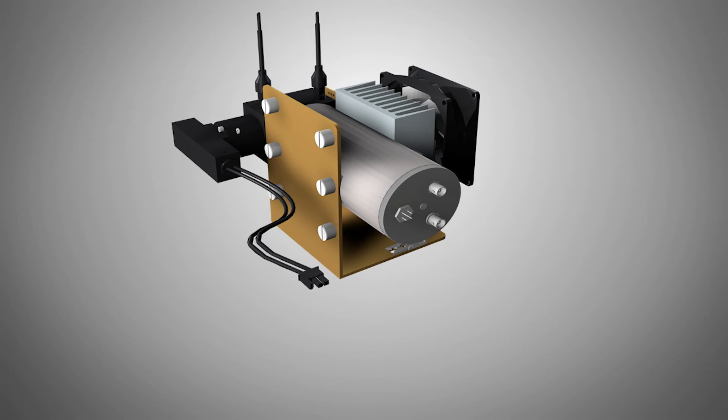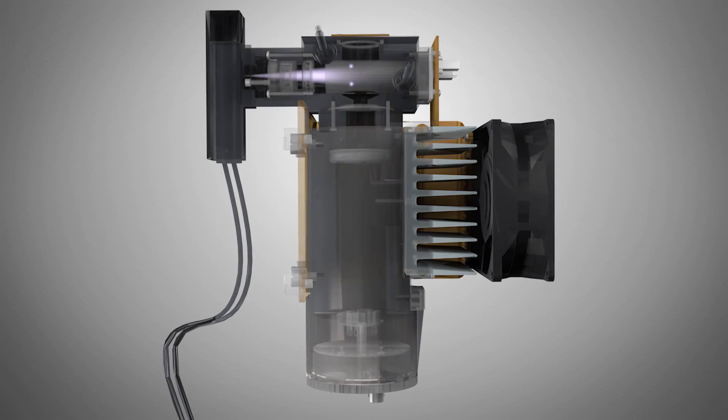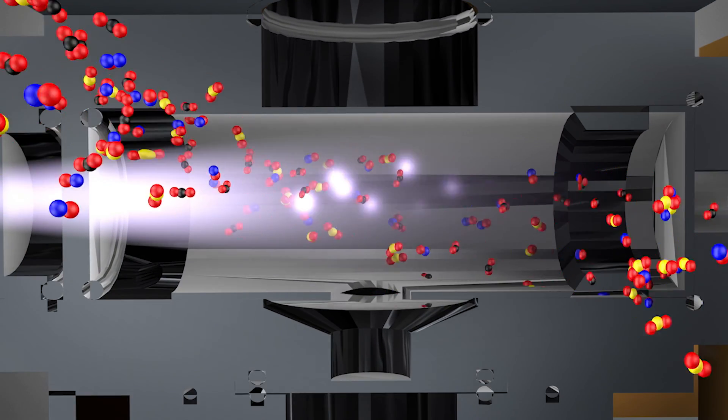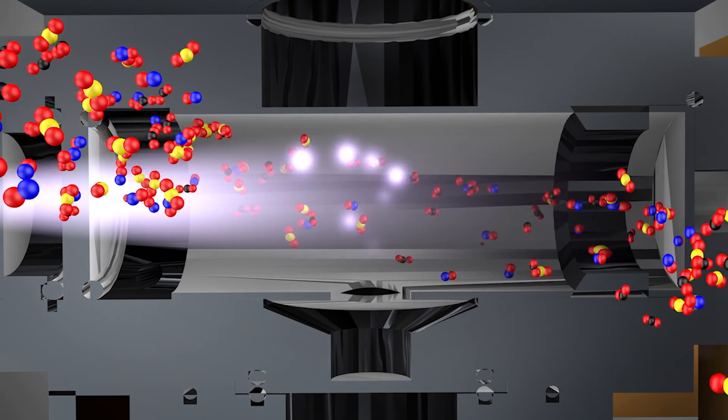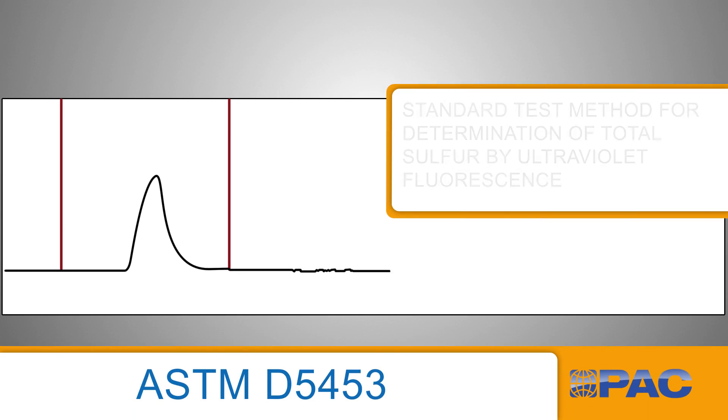The sample is exposed to ultraviolet light, which excites any sulfur dioxide present. Upon returning to a stable state, energy is emitted as a flash of light, which is measured by a photomultiplier tube. The amount of light emitted is proportional to the amount of sulfur in the sample. The detection method is based on primary test method ASTM D5453 for high correlation to laboratory results.